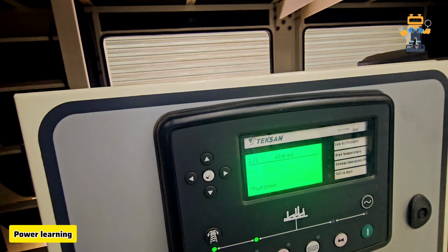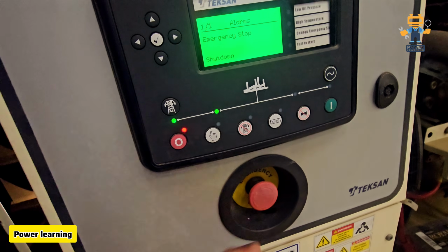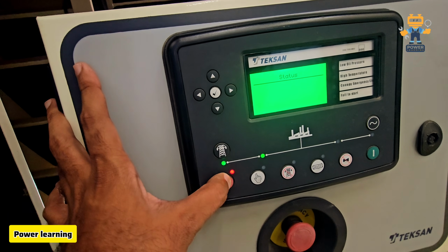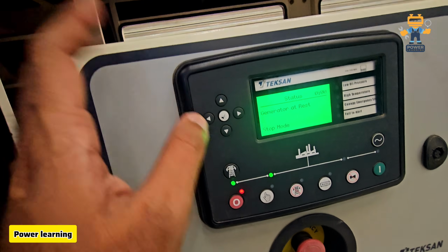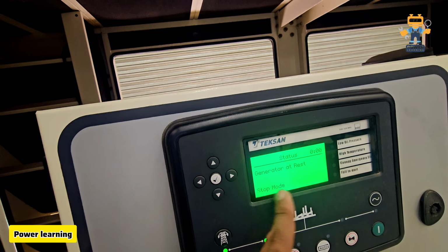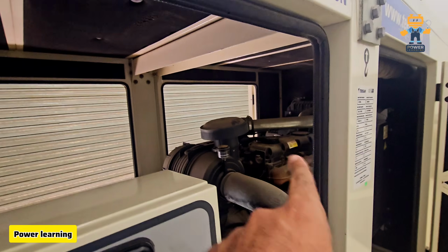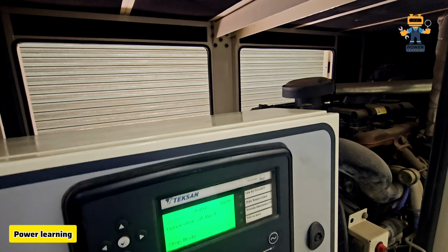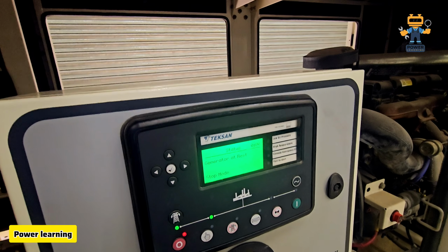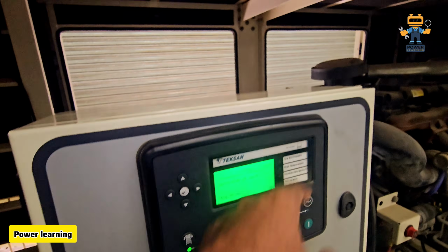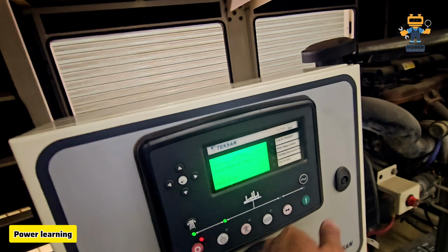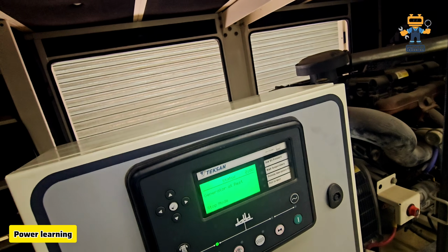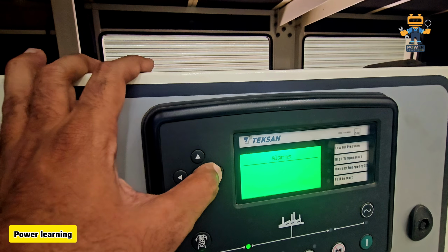How to reset this alarm? We need to make it normal and press the reset button. So the alarm is reset. But if there is an oil pressure or high temperature alarm, you have to fix the generator first, then reset and start. This I made for testing only. But if there is a critical alarm, don't reset and start. It will shut down and damage the engine. So now you know how to check the alarm.